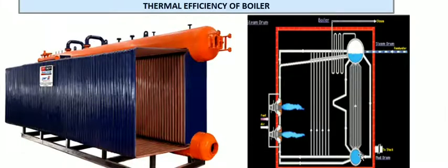So now we see the steam path, water path, flue gas path, and the oil path. Whenever we require saturated steam directly for heating purposes, we can take it directly from the steam drum. If we need superheated steam, we take it from the superheater outlet coil. From the header, we can line up to the turbines. There are saturated turbines and superheated turbines also. Based on the requirement, we can line up. For heating purposes, we have to utilize the latent heat of condensation, and for effective heat transfer, we need to supply saturated steam only.